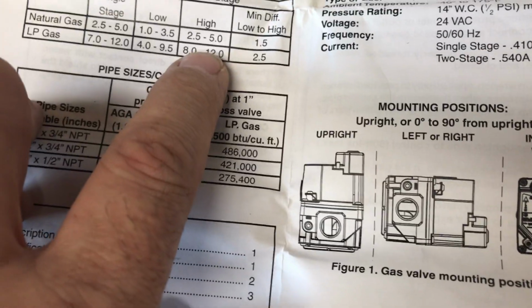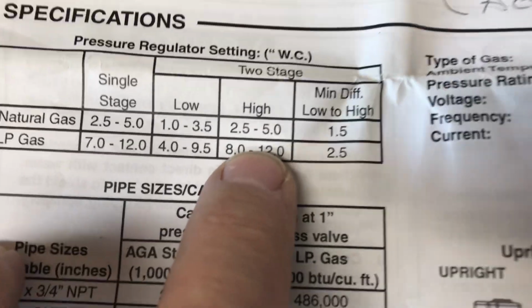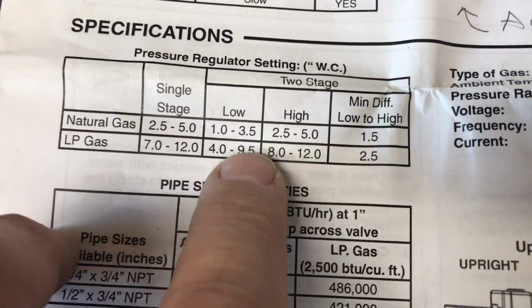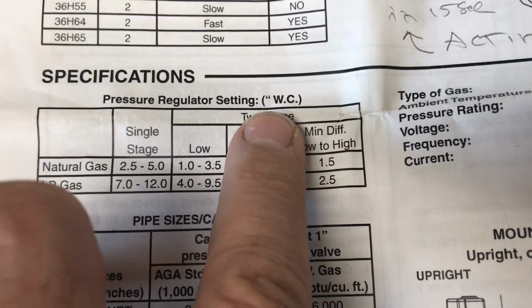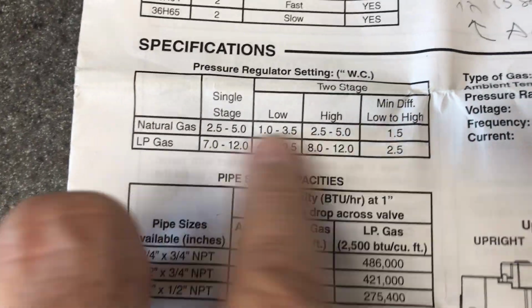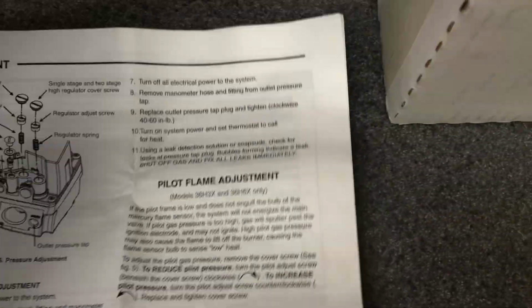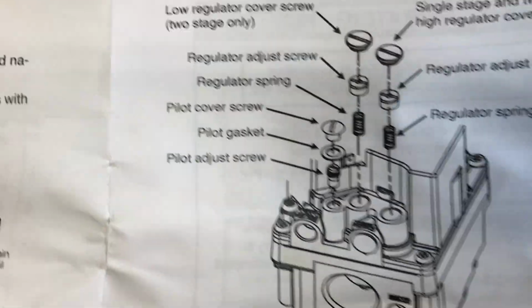So it starts out with 4 1/2 inches water column. And after 15 seconds, it drops down to 3 inches of water column. So that's for a two-stage. This part number does not indicate a two-stage. So I don't understand.